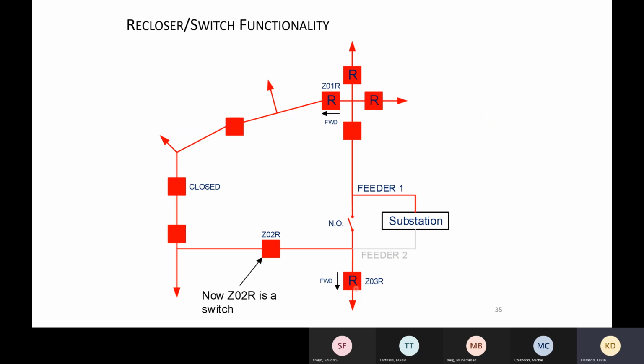So it's actually a 10-year program to mitigate all the fire risks on our system, but we were able to make a huge jump from 0 to 100 devices in less than a year. And it was all because we already had microprocessor-based reclosers out on our feeders.